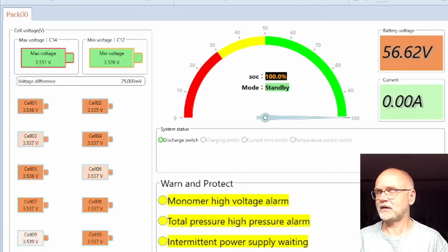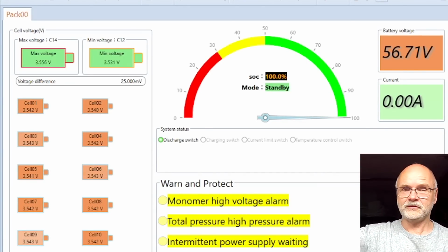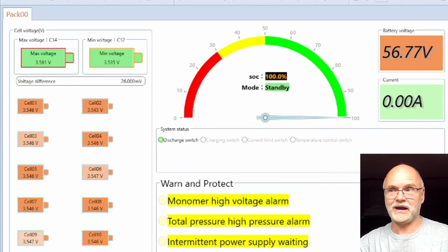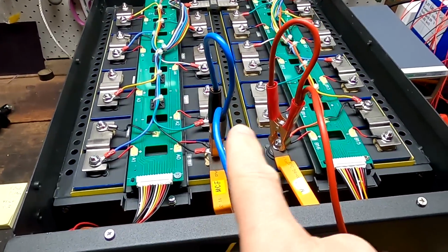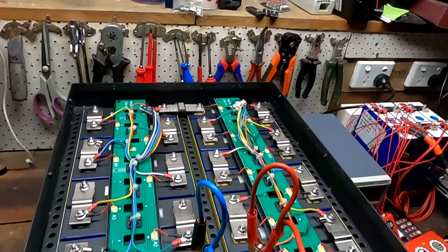Not good. I want to increase the voltage again to 56.8, which is 3.55 - is that correct? I think it is. Okay, so we don't see any current on the BMS because we are bypassing the BMS. The BMS does not allow any further charging, nothing, right? So you can see here negative and positive are directly connected to the battery, and the BMS is only monitoring the cell voltages, but it is still using the internal balancer, of course.